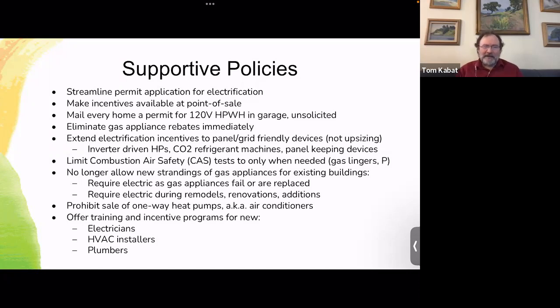We're also finding that combustion air safety tests are being required in cases where they shouldn't be. If you no longer have a combustion device in that building or room, you don't need a combustion air safety test—there's reform needed in the rules for when to apply those tests. Also, if you're not changing the pressure in the room, you don't need that test even if a gas device is left. So if your heat pump water heater is fully within the garage, it's just circulating garage air through itself—it's not drawing a vacuum on the garage or pressurizing it.